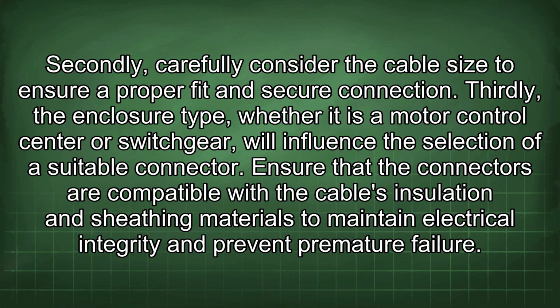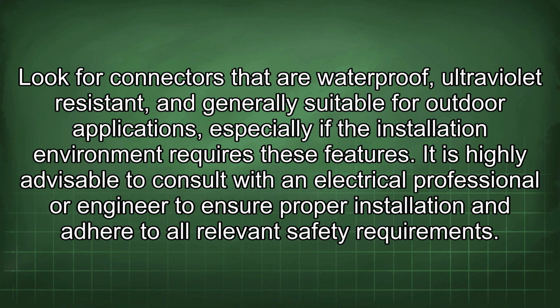Thirdly, the enclosure type, whether it is a motor control center or switchgear, will influence the selection of a suitable connector. Ensure that the connectors are compatible with the cable's insulation and sheathing materials to maintain electrical integrity and prevent premature failure. Look for connectors that are waterproof, ultraviolet resistant, and generally suitable for outdoor applications, especially if the installation environment requires these features. It is highly advisable to consult with an electrical professional or engineer to ensure proper installation and adhere to all relevant safety requirements.